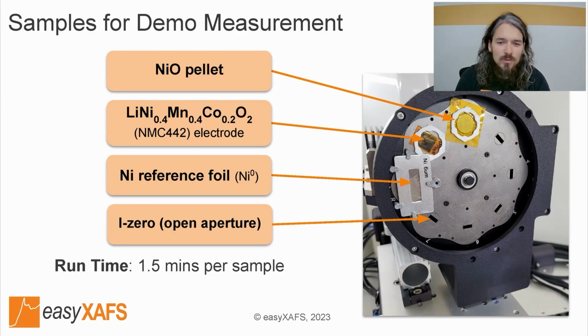For the demonstration, we'll be measuring at the nickel K-edge. So we'll measure 3 samples: reference nickel metal foil, an NMC 442 electrode sealed in Kapton, and a pellet made from nickel oxide mixed with binder. We'll measure 1.5 minutes per sample, and then do the same thing through an empty sample wheel spot for the I0, and then we'll go through those results together.